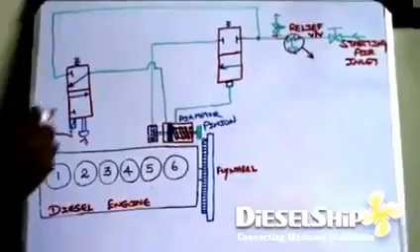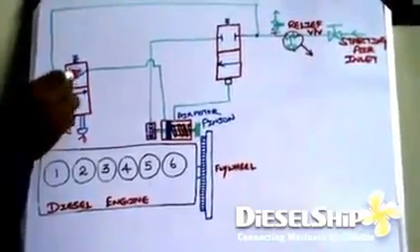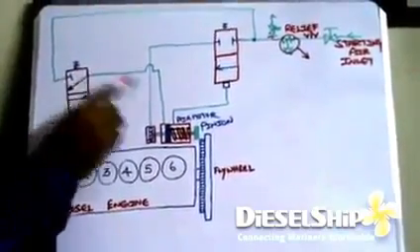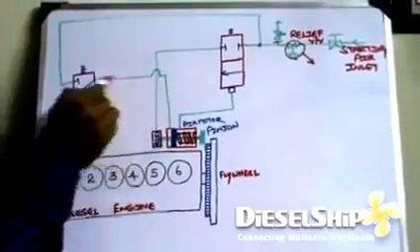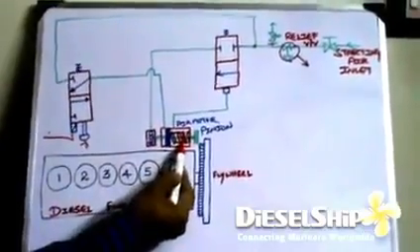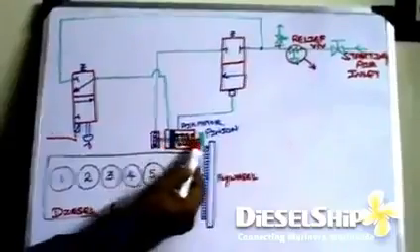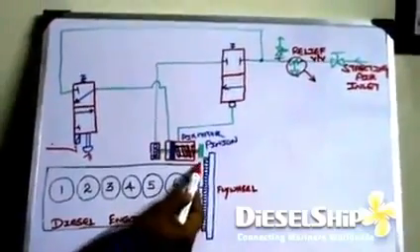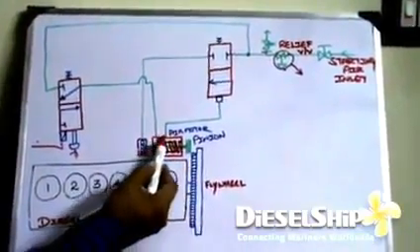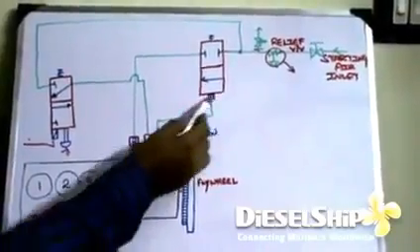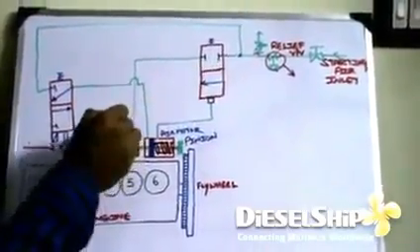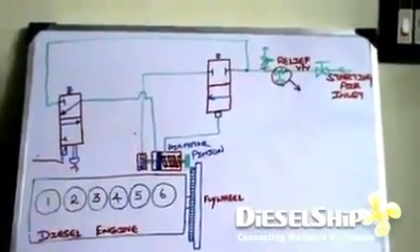Once it gets deactivated, the valve gets shifted, the air behind the piston gets drained, so the piston due to the spring force retracts, thus the pinion is withdrawn from the flywheel, and the air access is shut off, which means the air to the vanes or the air motor is cut off in this place.